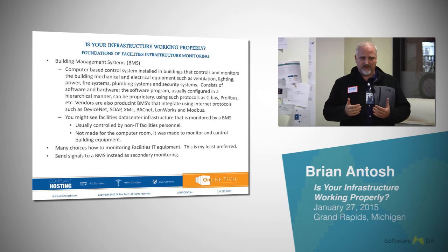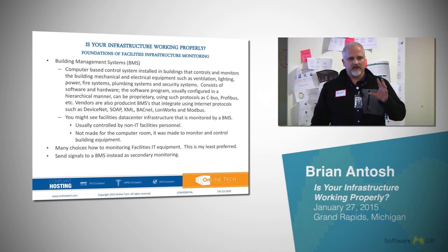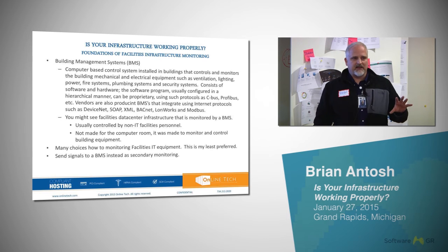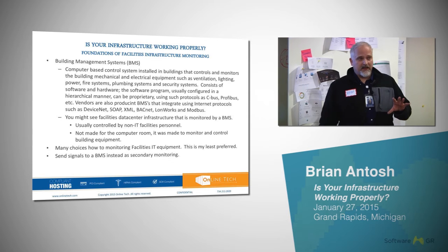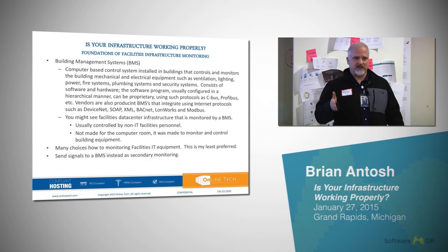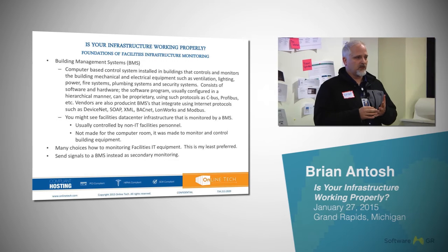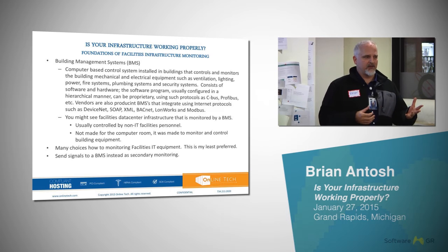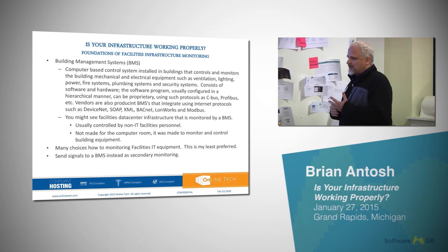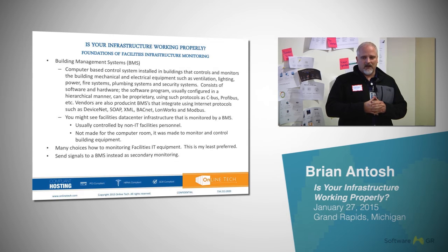What I've seen out there for some data centers, and this isn't so much the case nowadays, is a building management system controlling data center infrastructure. And in every case that I've seen, it's just a big mistake. The reason why is because someone else, outside of IT or IT facilities, it's probably straight facilities, is controlling it. So now you have these lines of demarcation that are gray. When something breaks, who's responsible for it? The right people don't get the right information. These systems weren't made for CRAC units or UPSs, and now all of a sudden they're monitoring them, so they had to kind of develop. All the ones I've seen, BMS systems are complex and hard to use. So I'm not a proponent of the building management system controlling data centers completely.